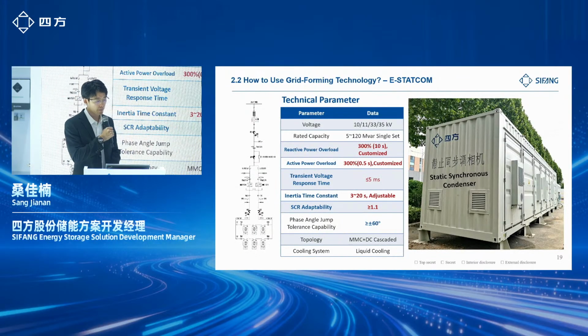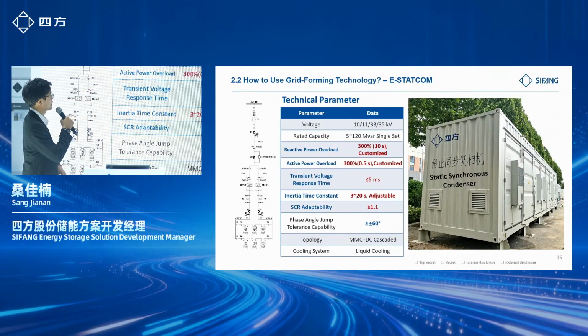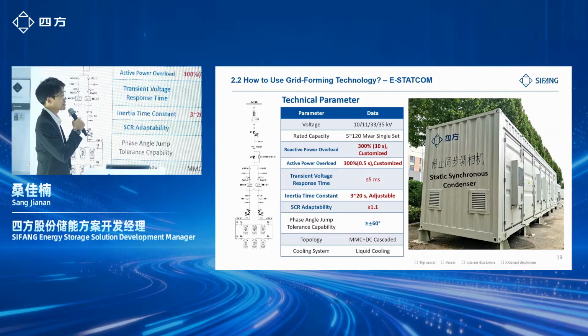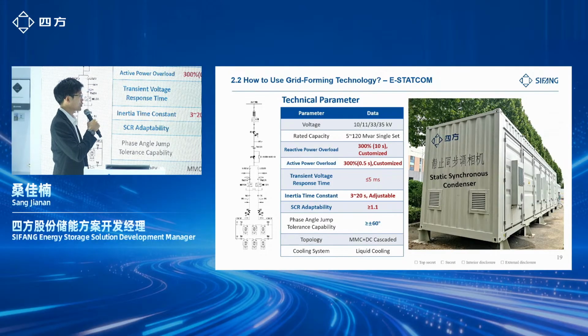And here are the main parameters. It can be used at voltages of 10 kV to 35 kV, and the rated capacity can be 5 MW up to 120 MW. No matter reactive power or active power, it can overload, and it can also be custom sized. For transient voltage, the response time can be less than 5 milliseconds. If any failure happens in the grid, our E-STATCOM can react quickly to support the voltage up to 90% within 5 milliseconds. The inertial time constant can be adjustable from 3 to 20 seconds. Even at an SCR equal to 1.0, it can still operate.